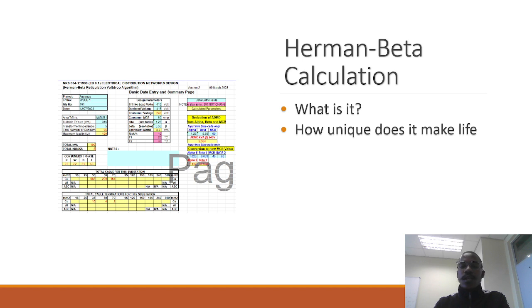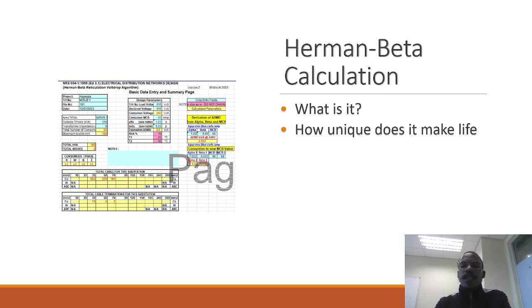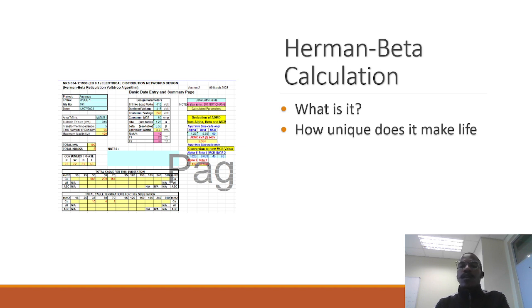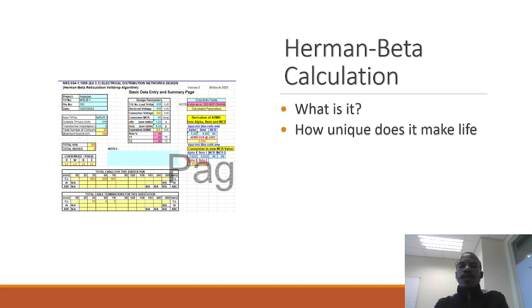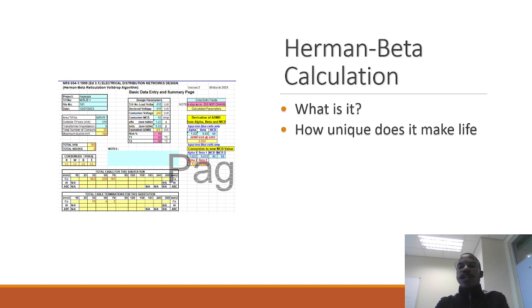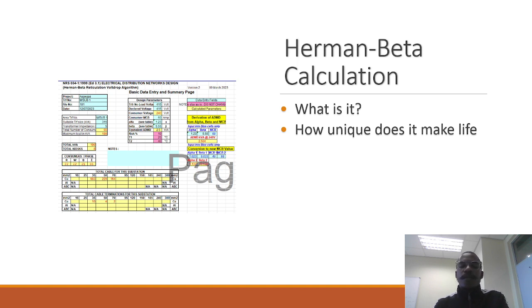In reticulation, the main thing we want to do is calculate the different voltage drops so that the electricity gets to its distributors at the safe operating level. We usually do this in Excel using a particular Excel sheet called Herman Beta Calculation. This is a standard calculation I've seen used in all areas. I will record another video as to how we use the Herman Beta Calculation table. It tells us the cable supply to that particular substation, the size of it, how much length you need, and the ADMD. ADMD is the After Diversity Maximum Demand. I'll record another video explaining ADMD and what it is.